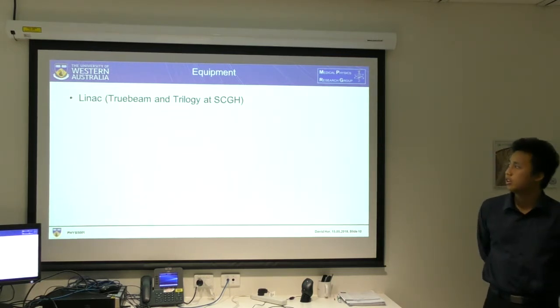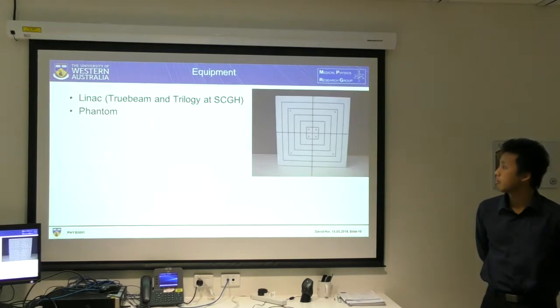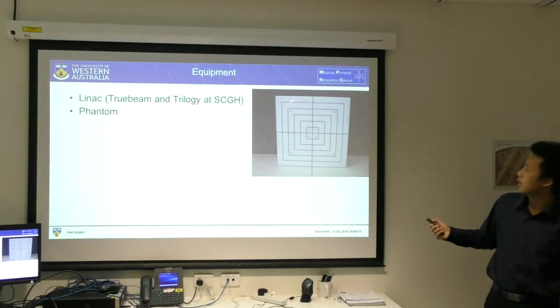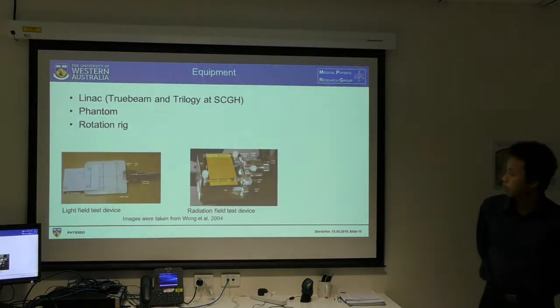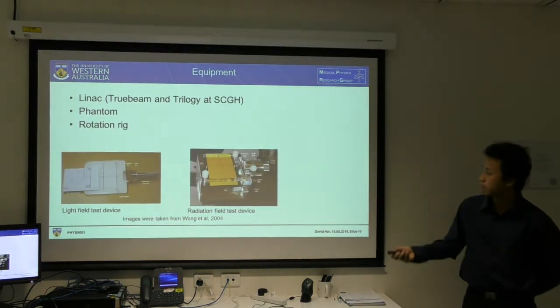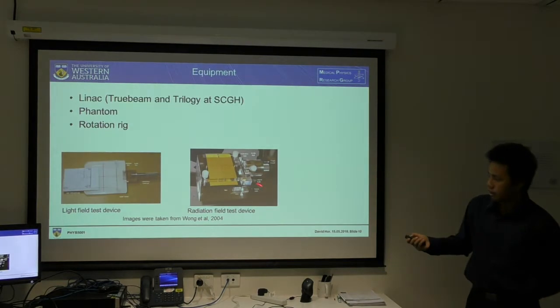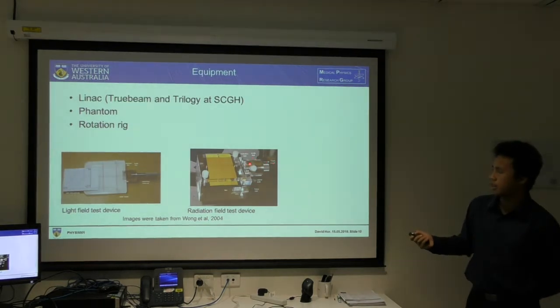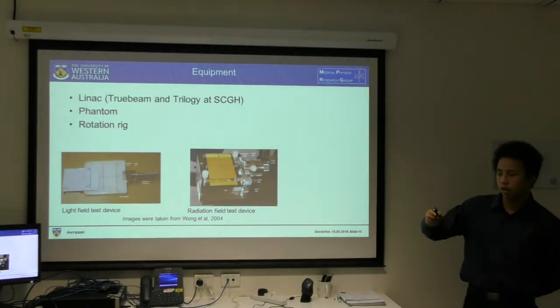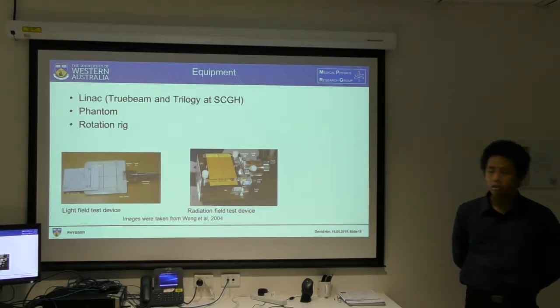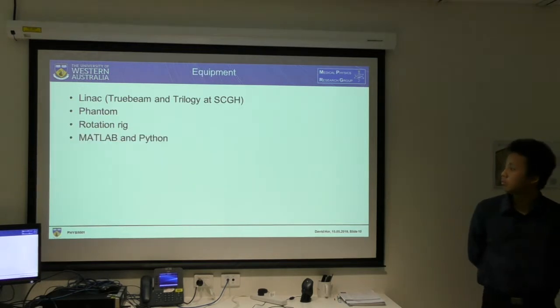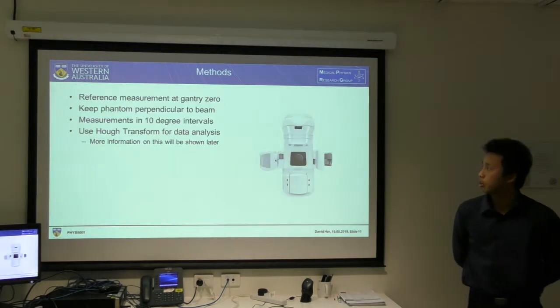The equipment includes the Varian TrueBeam and Trilogy LINACs located here, a phantom with eight ball bearings as shown, and the rotation rig from Wong — that's the light field and radiation field test fixture which connects to the couch, with dials that you rotate to try to match the perpendicular angle. MATLAB and Python are equipment as well.